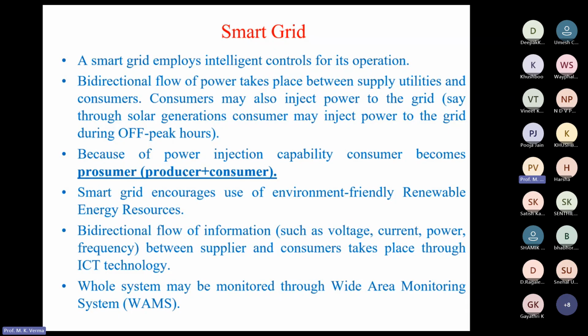Similarly, on the consumer side, you can have a smart metering scheme through which data can be transmitted in a bidirectional fashion. And the whole system can be monitored through a wide area monitoring system using synchrophasor technology by means of phasor measurement units.